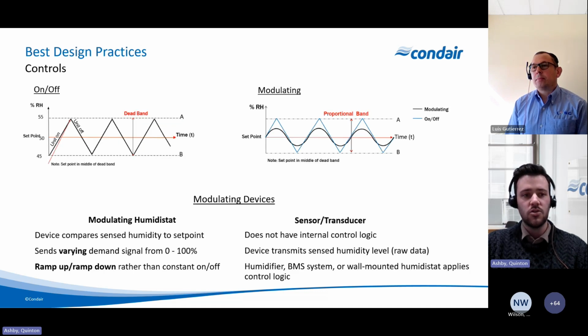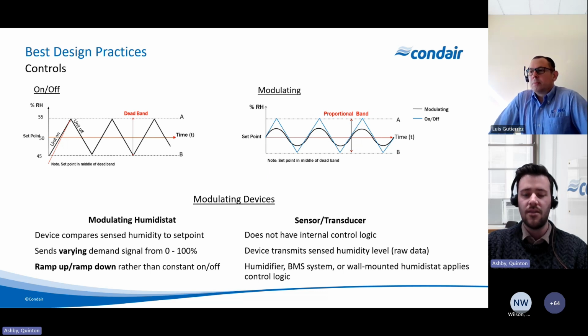2 types of controls: we have on-off or modulating. We highly recommend modulating, as it can actually increase the accuracy of the humidification. And in terms of modulating, we have a modulating humidistat versus a sensor and transducer. The only difference there is where the logic is being applied. The humidistat applies the logic at the stat itself, and the sensor sends a signal to the humidifier, which then does the logic.